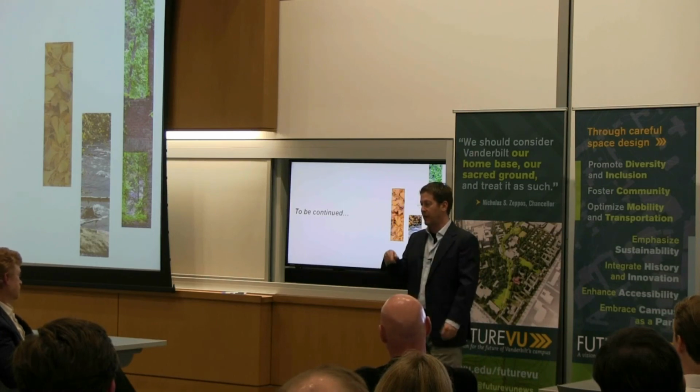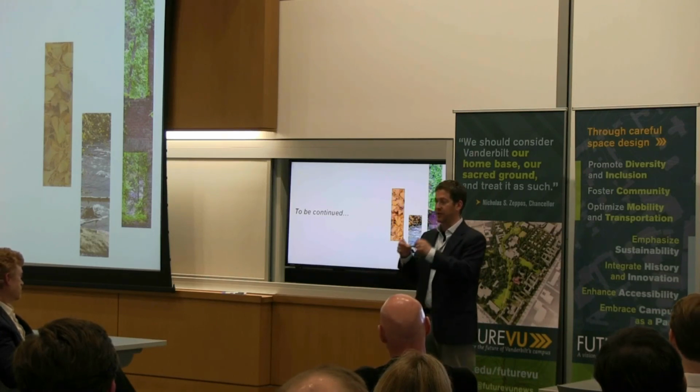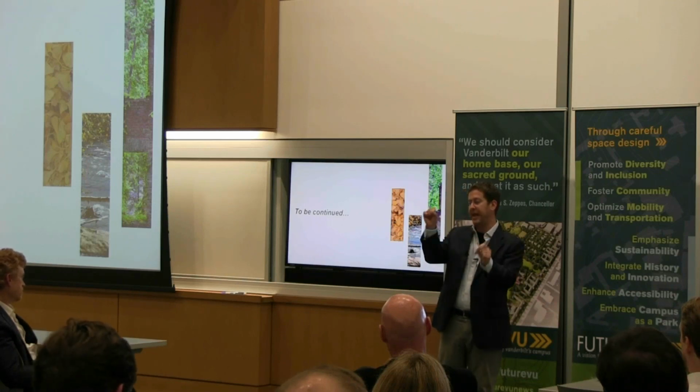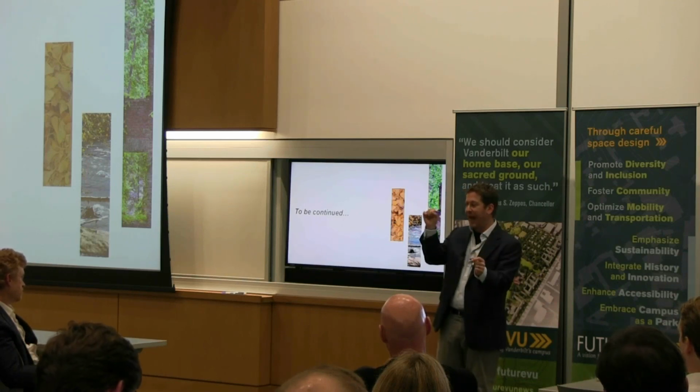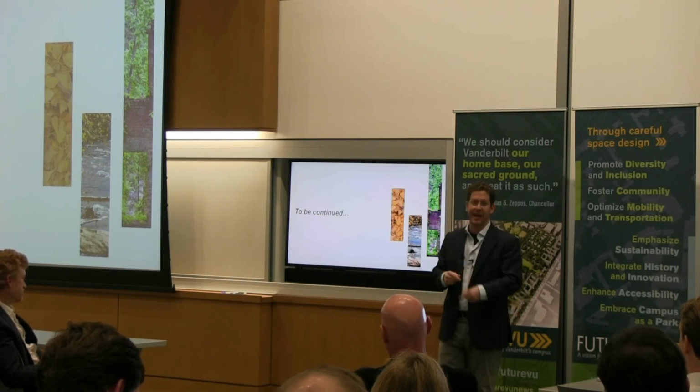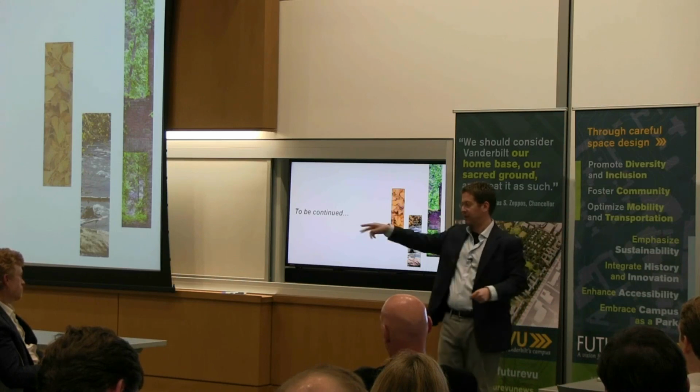The way we're getting around it in the building is that the temperature of the slab, in terms of its cooling capacity, is pegged to the dew point in the building. So we're maintaining a delta of at least, I think it's 1.5 degrees, between the two things, so we don't end up with the potential for condensation. But that ties back, like I said, pull a thread, everything else unravels.